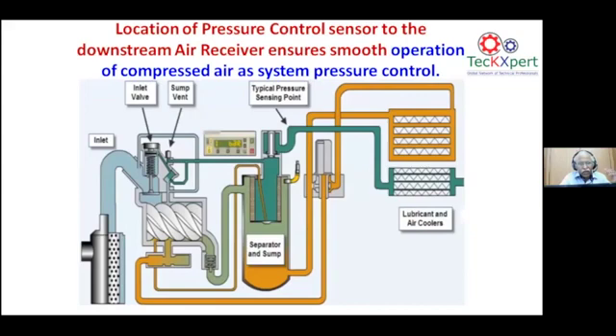Again, coming back to the compressed air hood, you can see the typical pressure sensing point, which is just taken at the elbow point of the oil reservoir. This is a point of turbulence. All the imported compressors, the OEMs can definitely think over it and see to it that it is kept in the pipeline on the delivery line, where you have a streamlined airflow, streamlined pressure, and no pulsation in the pressure. Definitely, this will pay off. This will reduce the energy consumption of the compressor. The wild fluctuation of compressor kilowatt will not be there because the pressure sensing is also taken from a steady plane.